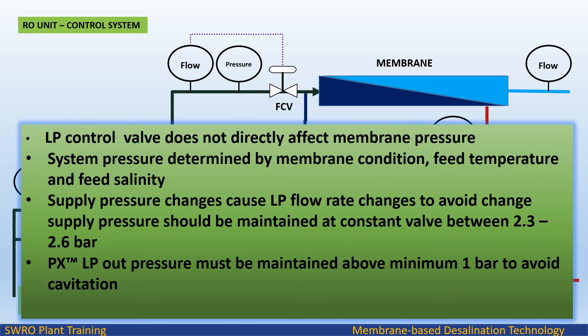The LP control valve does not directly affect membrane pressure; system pressure is determined by membrane condition, feed temperature, and feed salinity. Supply pressure changes cause LP flow rate changes, so to avoid this, supply pressure should be maintained at a constant value between 2.3 to 2.6 bar. The PX trademark LP outlet pressure must be maintained above a minimum of 1 bar to avoid cavitation.